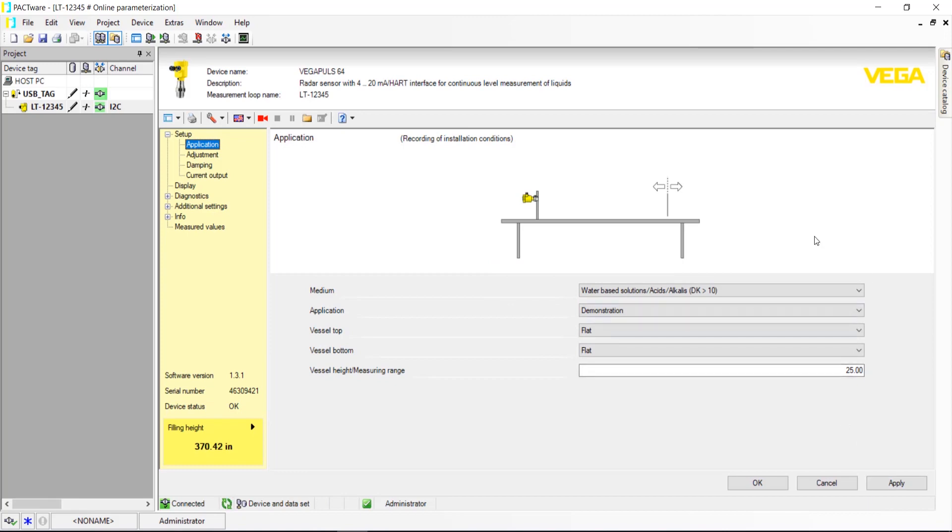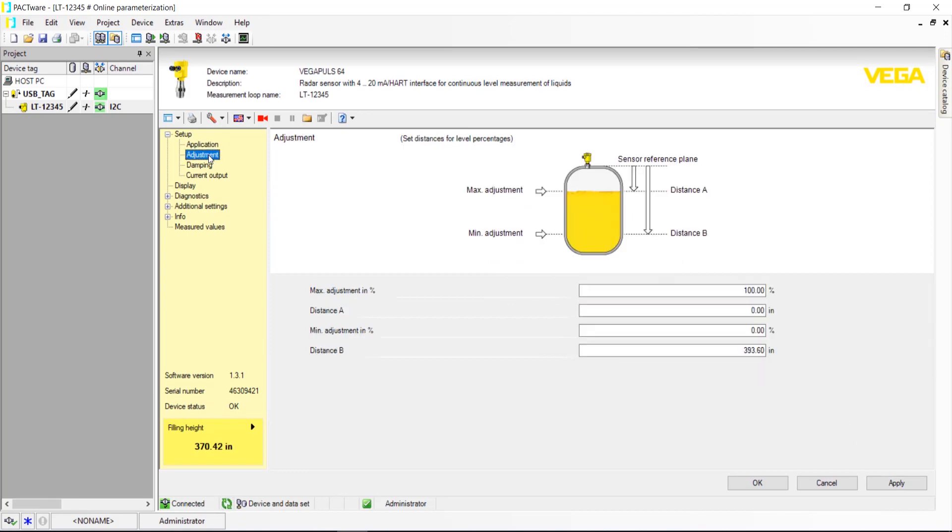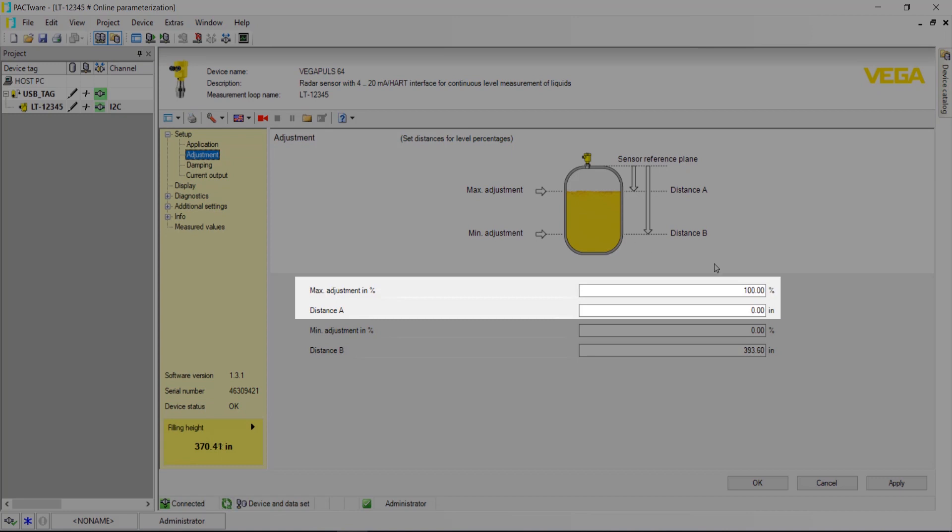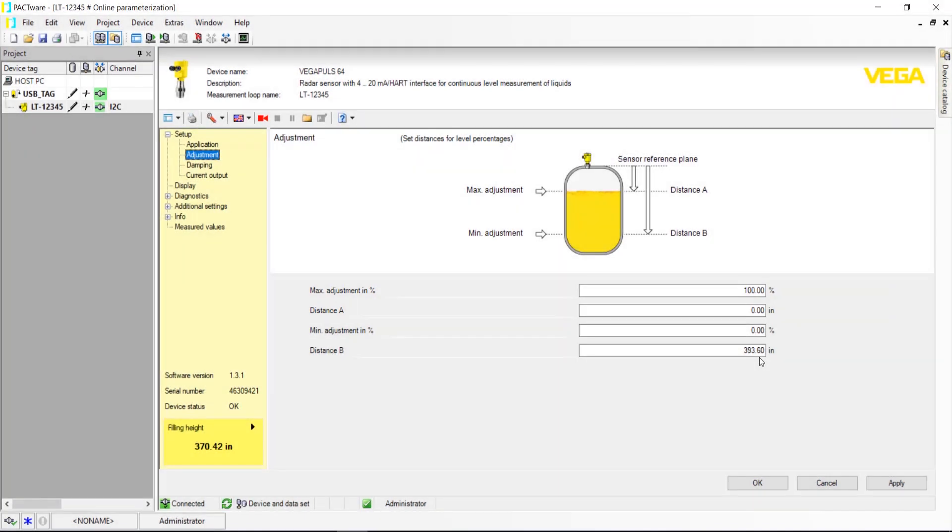Next, move down the Setup tree on the left side to Adjustment. Distance A is the distance from the radar reference point to where you want your 100% fill point, or where the sensor will output 20 mA. This number should not be zero because that would result in product touching the radar sensor at 100%.